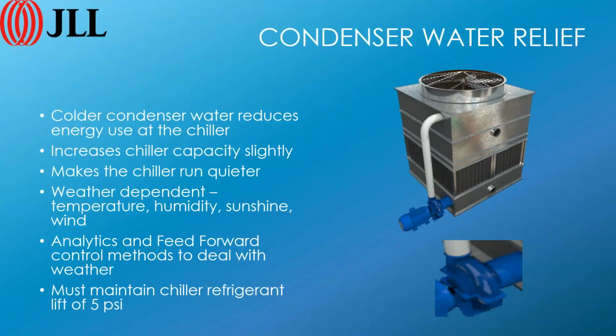Now the third portion of this is condenser water relief that we want to look at. Under condenser water relief, we want to look at colder condenser water. And that colder condenser water helps us get some additional chiller capacity. Inside the condenser, we have some very hot gas, and by having colder water going in, we're removing that heat and turning it into cooler refrigerant quicker. And that helps us get to a point where, instead of having warm liquid going through an expansion valve and flashing a bunch of it off, we can flash just a little bit off, because we've made the liquid cool enough.